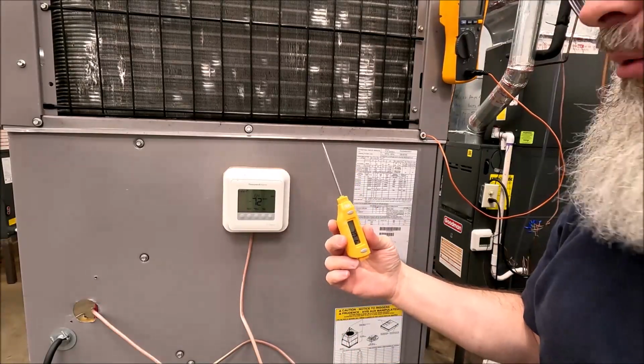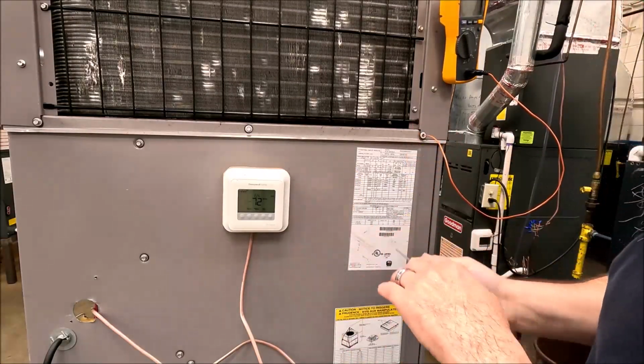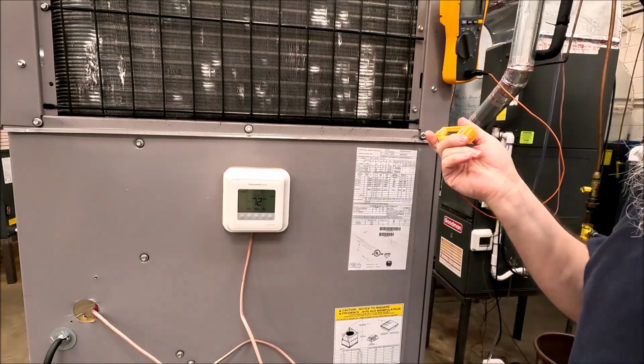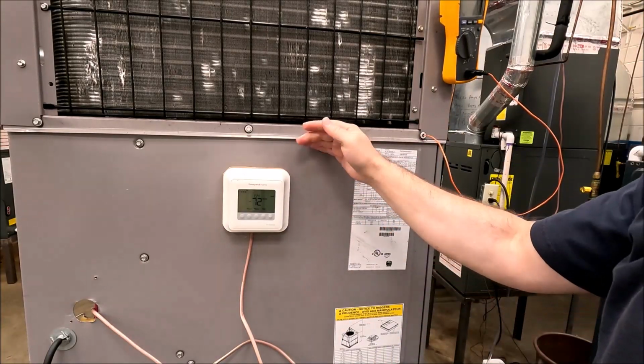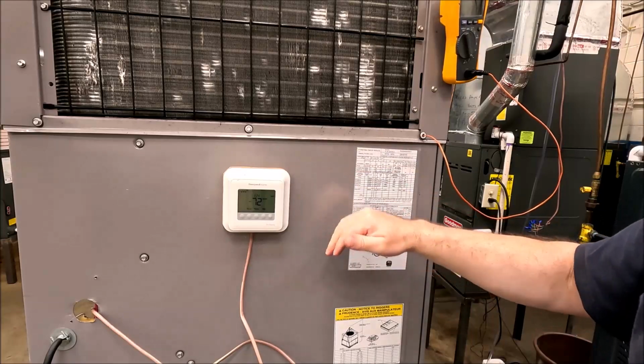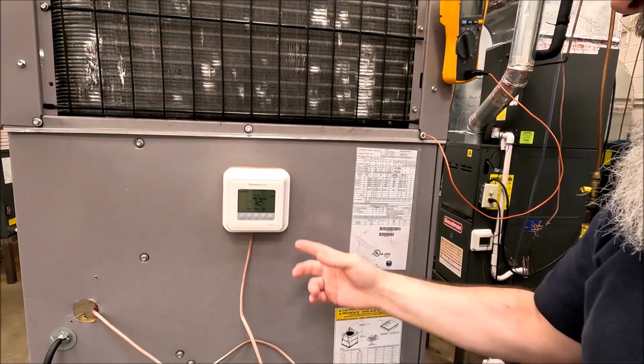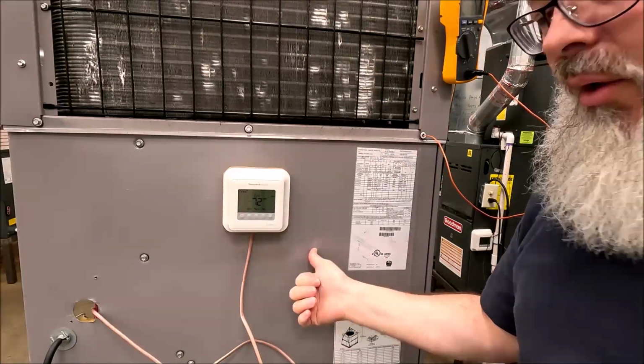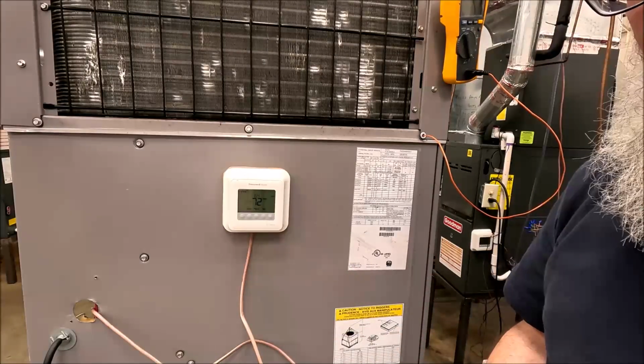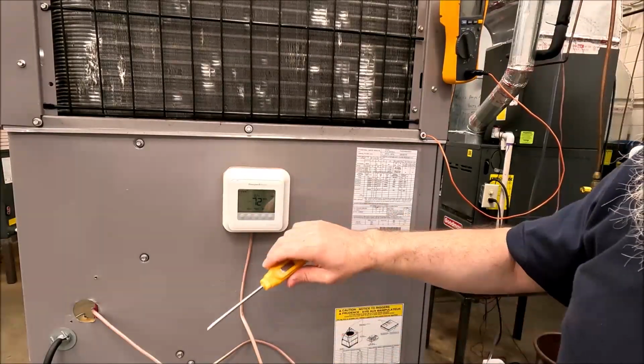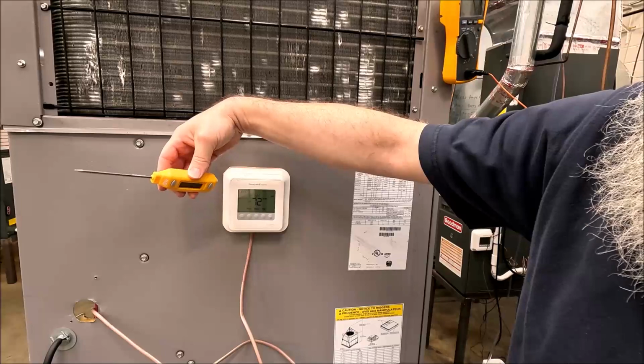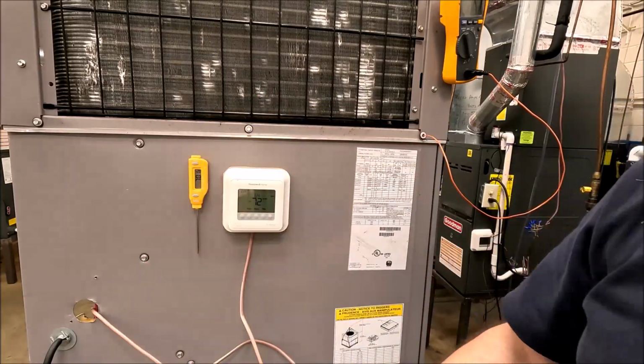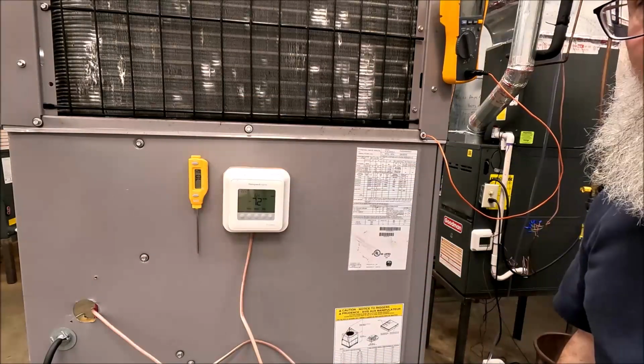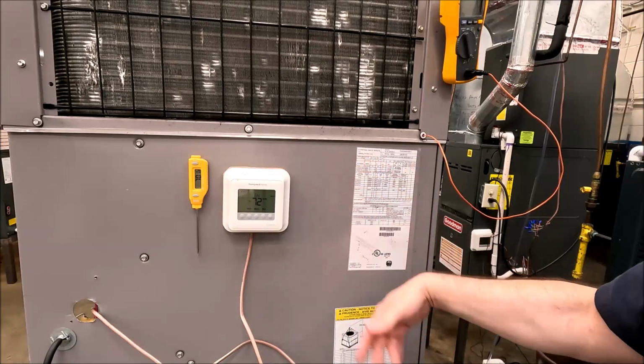taking your air probe and trying to stick that way. If anything, you're going to go straight into that insulation that's underneath this metal that separates the two halves of the system. And I don't really like drilling holes in the side. It just kind of looks tacky, because a lot of people either use duct tape to cover it up or they don't have anything to cover it up. So it just gives you an access point for rain, bugs, whatever.